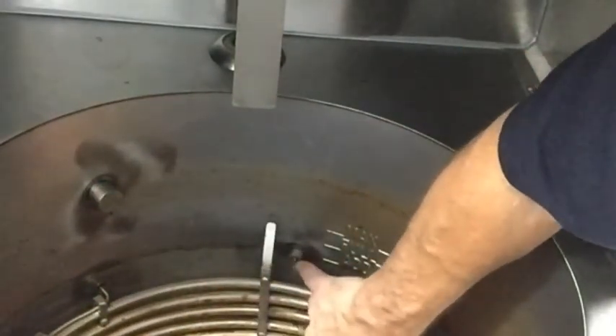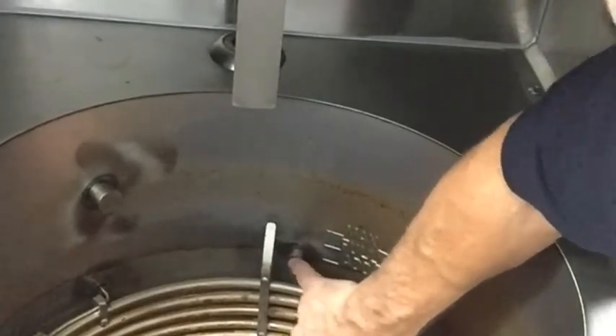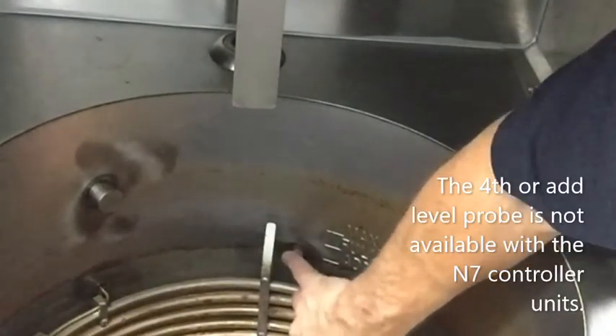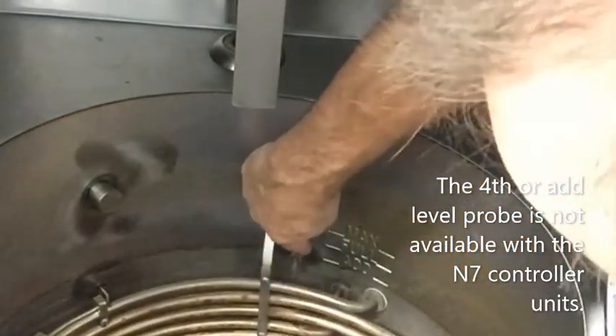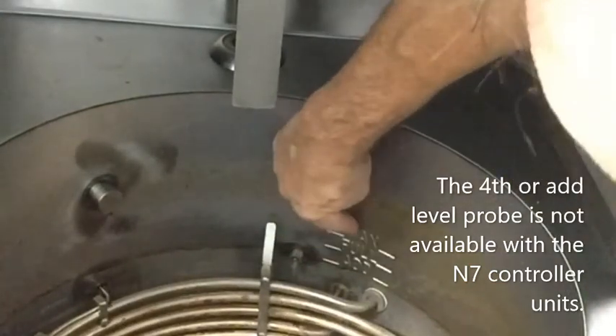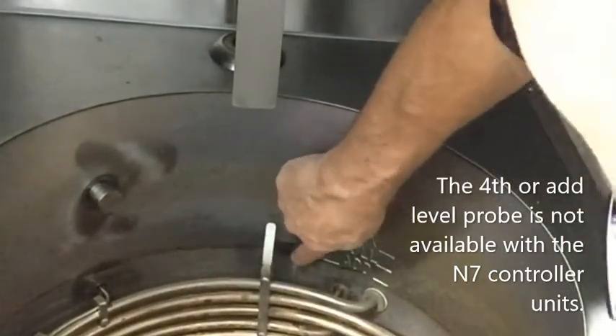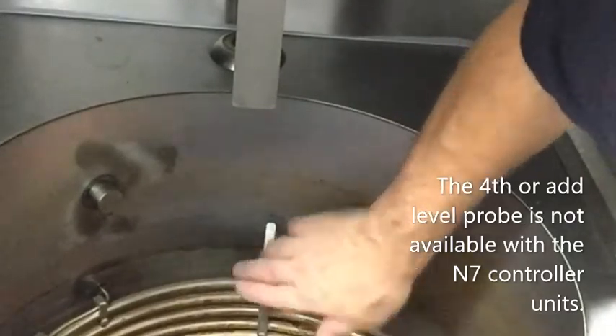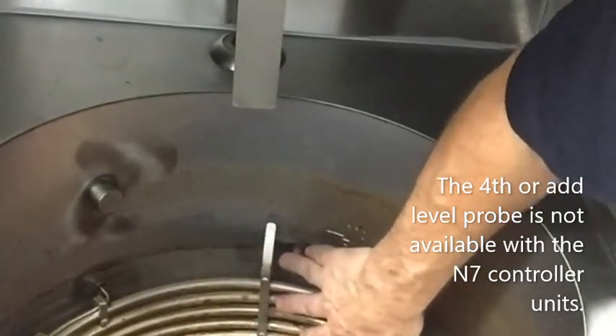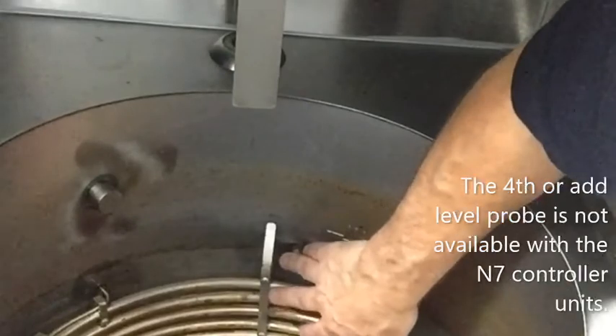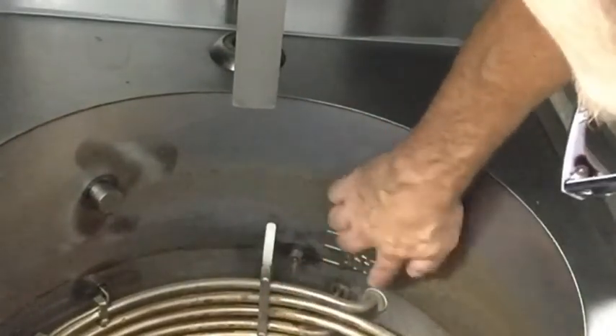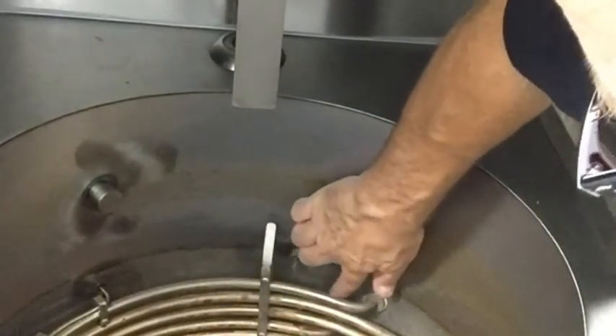This right here is what we call the 4th probe. This is your oil level probe. So if the oil level drops below, and you'll see that it's right here at the add mark, we've got max, full, add, but you'll see right here, that's where it's at. If it drops down below that, it will cause it to shut down. It will send a message to the controller and let you know. Right here, you can see just the start of it.